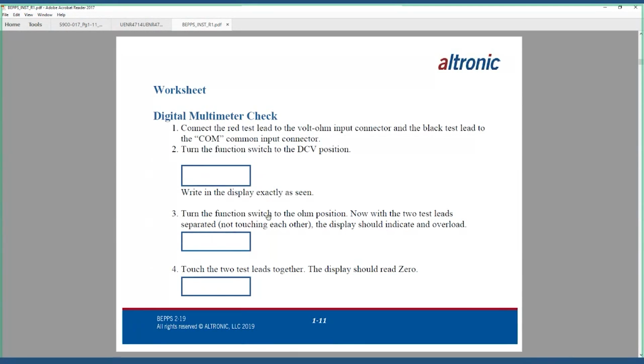Another thing you can do is turn the function switch to the ohm position, and with the two test leads separated, not touching each other, the display should read OL, which stands for overload. And if you touch the two test leads together, the display should read 0. But most people will find, and here's a really good point, that when they touch the two test leads together on their meter they do not get a 0 reading. The reason being is because the meter has a little bit of resistance built into it already. So do the probes, your meter leads. They have a little bit of resistance built into them. So again, this is a great way to test your meter before you start on anything to make sure your meter is in good working order.